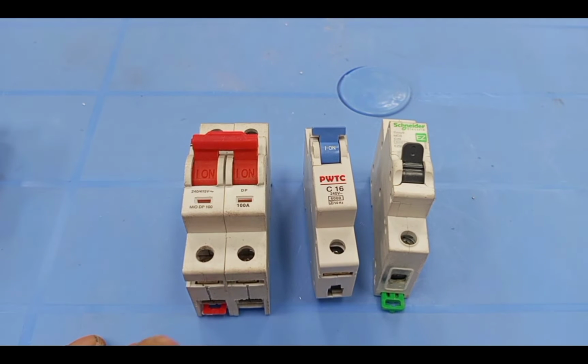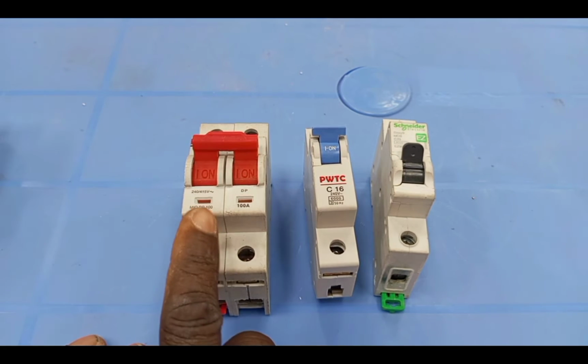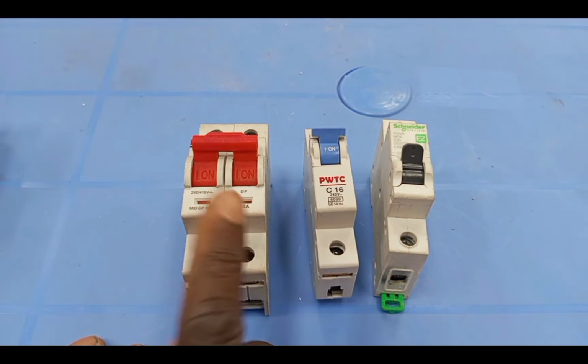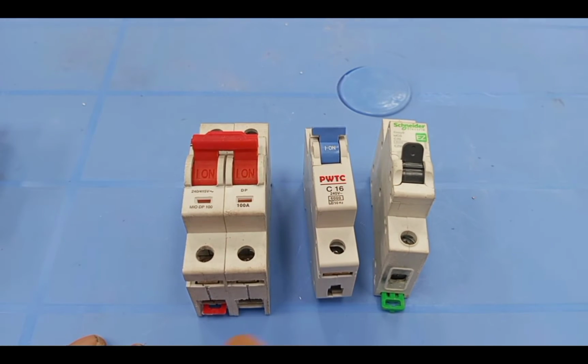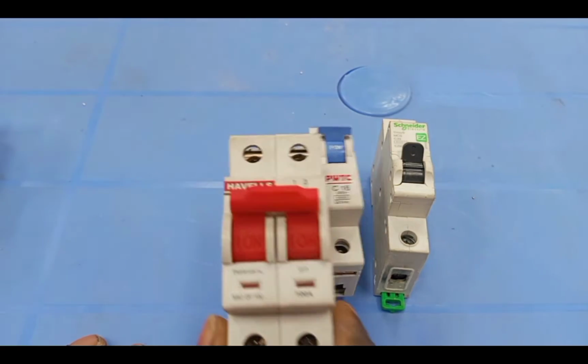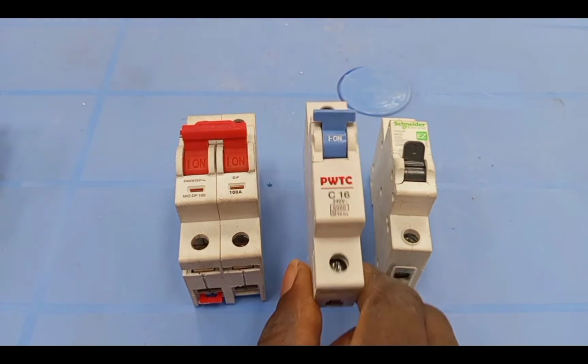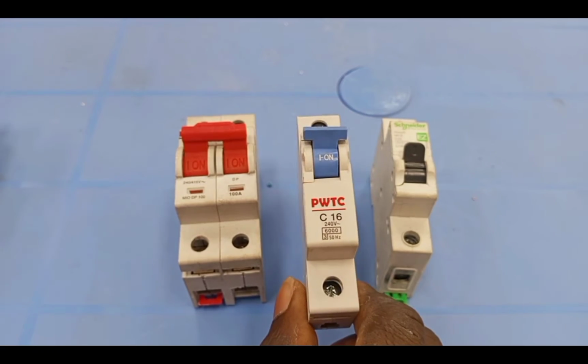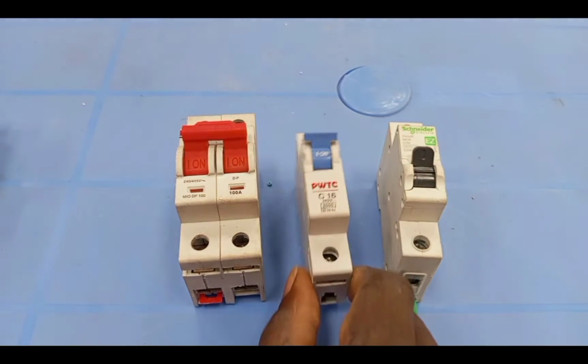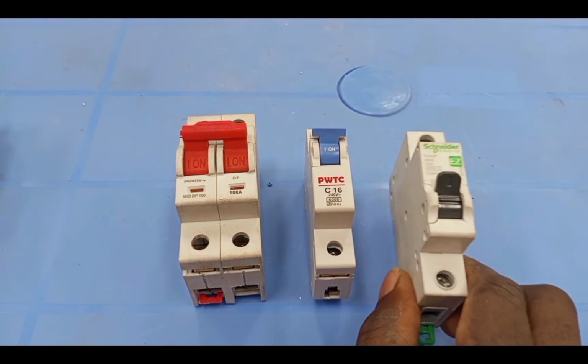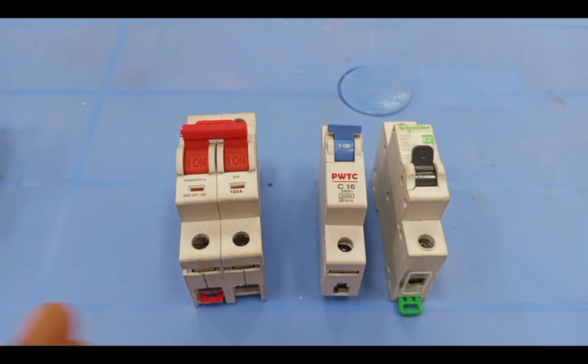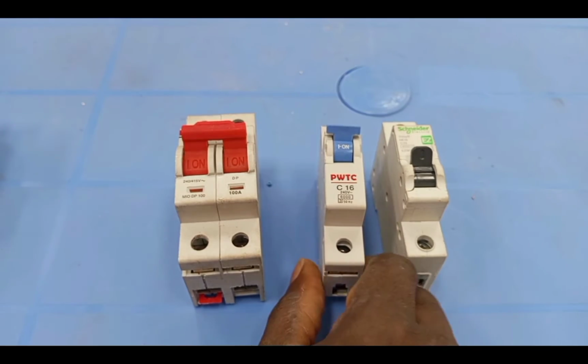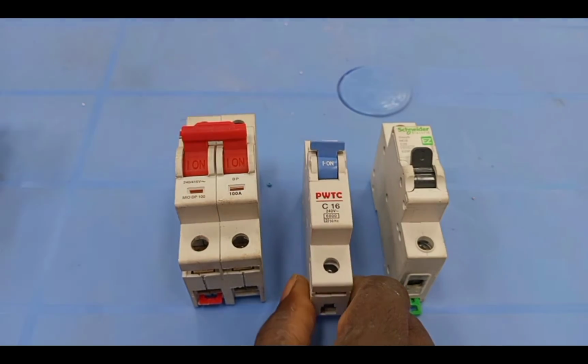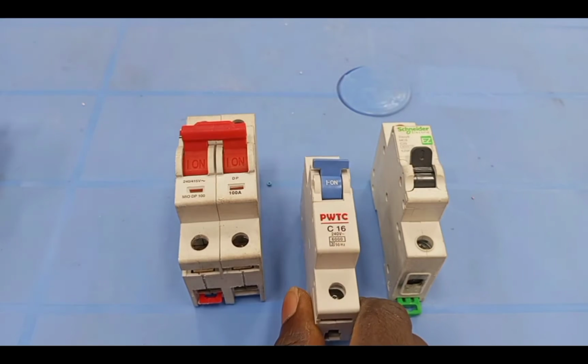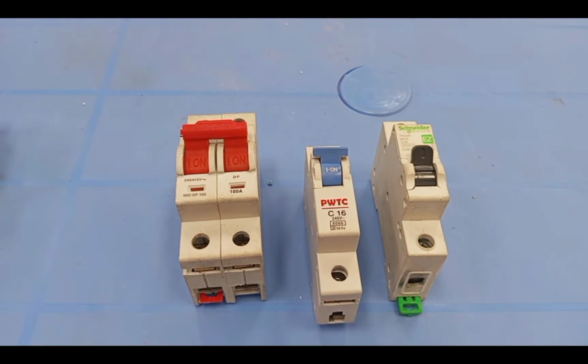All right. Usually, the main breaker, the breaker that is protecting the whole wiring, is usually a double pole breaker. Most of the time, depending on the size of the wiring, it is rated 100 amps. Then the single pole breakers protect the individual circuits. Depending on the number of circuits you have, you have a number of the miniature circuit breakers in your distribution box. So these individual breakers protect the individual circuit from short circuit and then overload.